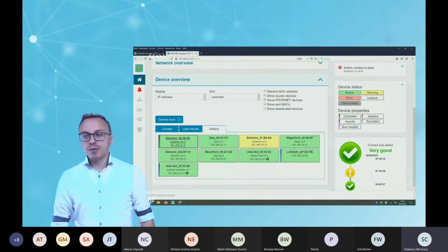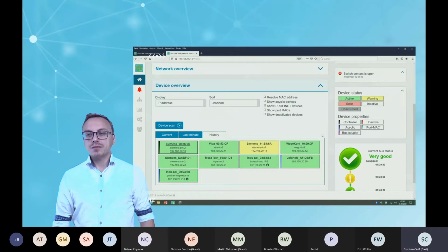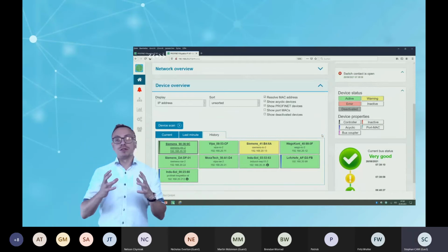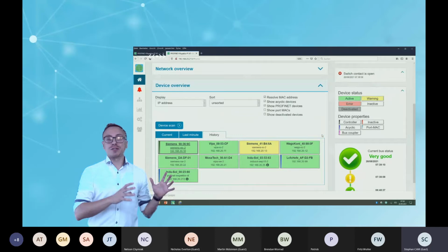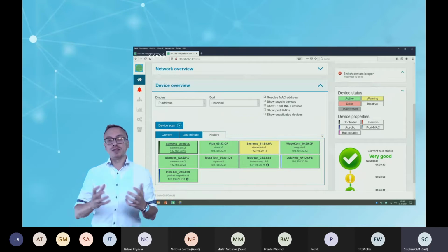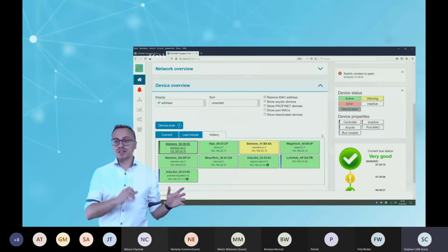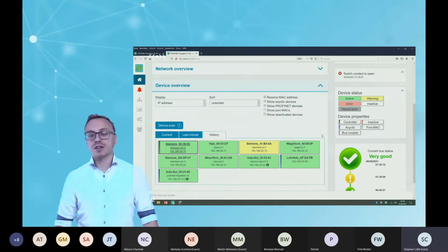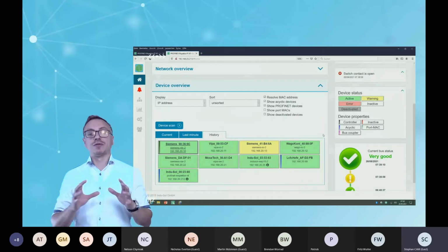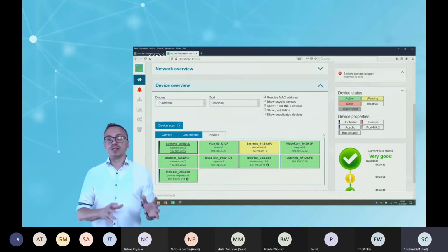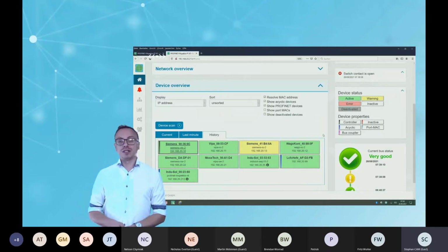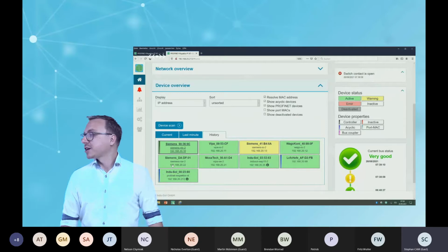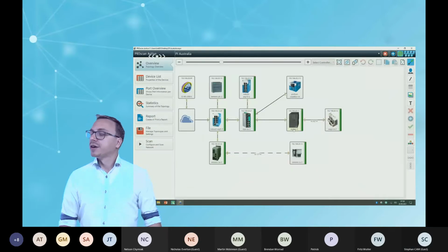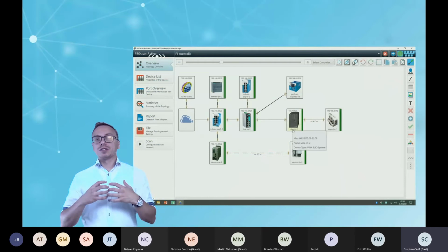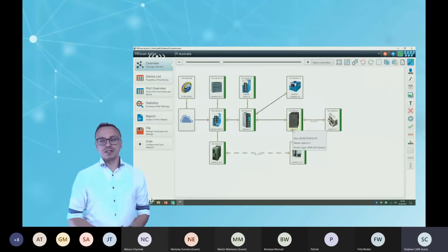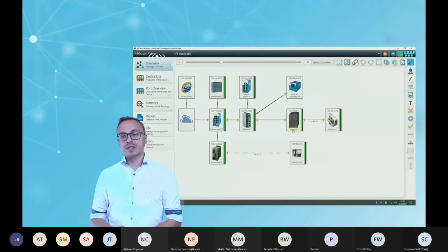The problem on bigger plants is that every time, now you know which device, but on big plants, huge plants, you don't know where this device is, or maybe it's not easy to find out where the real issue is if you have more than one device that is affected by this problem. In this case, as I said, you can use a topology scanner like ProScan Active. For example, this is now ProScan Active.